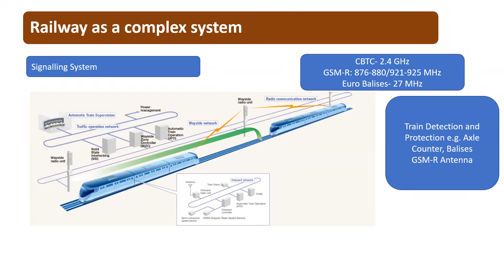Taking the power supply system as an example, which is a great contributor to electromagnetics in the low frequency range: substations receive high power, high voltage from the main lines and switch it down to the low voltage supplied for train operation. Substations are a great source of magnetic field, and there's a requirement in railways to keep the magnetic field below the limits set by international standard EN 50121.